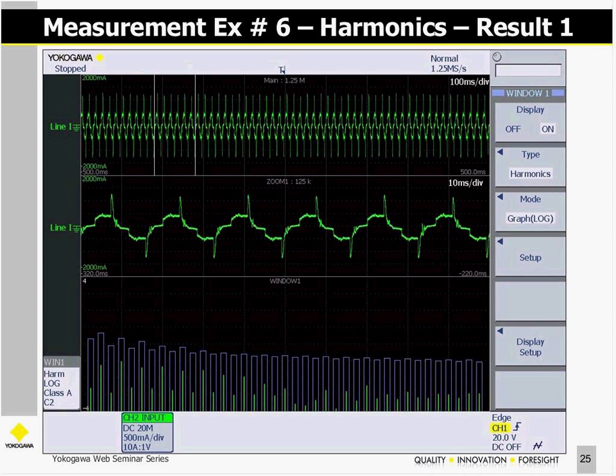The harmonics IEC 61000 test is very easy on the Yokogawa harmonics analyzer. When you come in here, you select the type of test. There's a class A test that we're running here, and that test is applied to certain devices, and the IEC defines these. So one class is maybe motors, another class is computers or consumer electronics. In this case, I'm running a class A test.